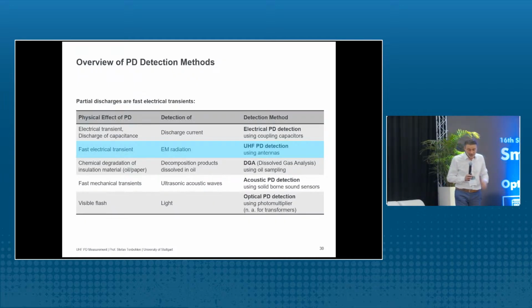So you can measure these partial discharges by different means. Normally it is done by a dissolved gas analysis. Dissolved gas analysis means you take an oil sample from the transformer and you analyze this oil sample in a laboratory, to see what gases are in the oil, and depending on the amount and type of gases you can decide: do I have a problem or is there no problem? So a problem can be a hotspot, partial discharge, and whatever. But of course this DGA does not tell you where the PD is, and also not how strong the PD is. Yeah? So it's just a very early indicator.